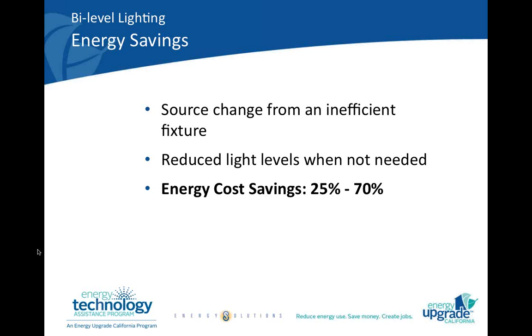However, it should be noted that a project with 25% energy savings may still be just as financially attractive as a project with 70% energy savings. To illustrate an example of when that may be the case, take a case where you have relatively low energy savings. You might have an existing garage that has first-generation T8 fluorescent lamps and old, relatively inefficient ballasts. In this type of situation, you have a potential to upgrade just the lamps and the ballasts in the fixture with new high lumen lamps and extra efficient ballasts that are bilevel capable. And in that type of case, you might have energy savings anywhere from 25 to 30%.